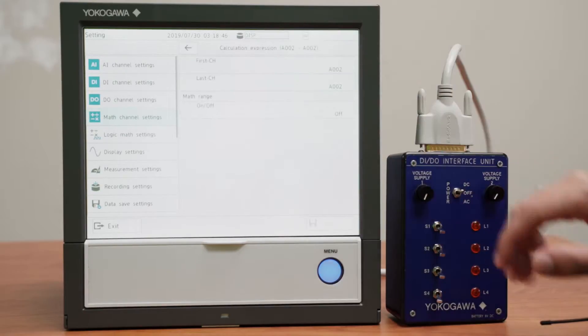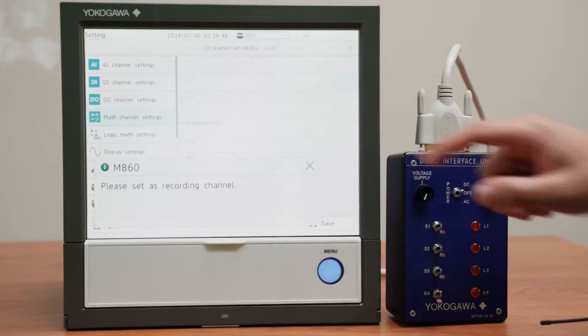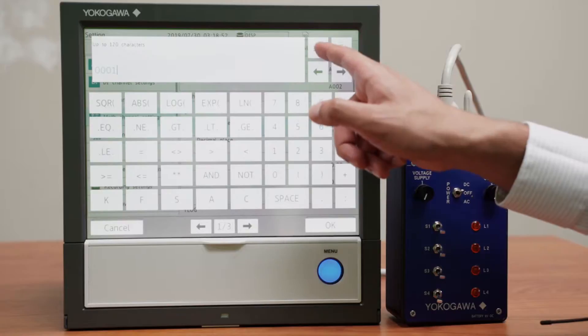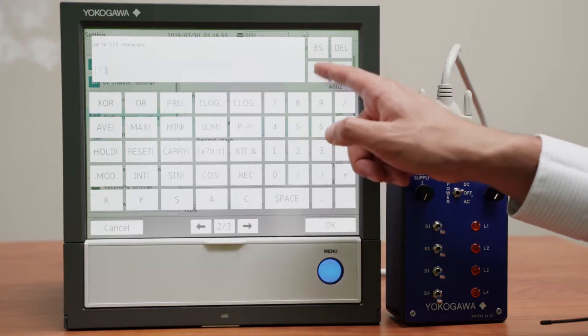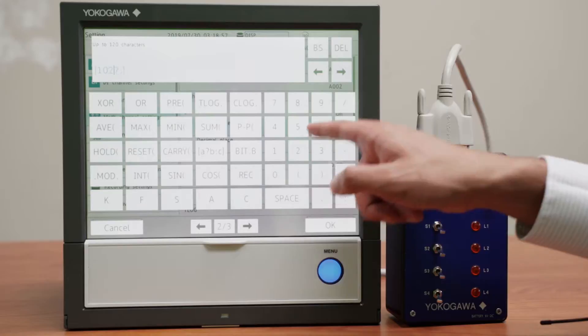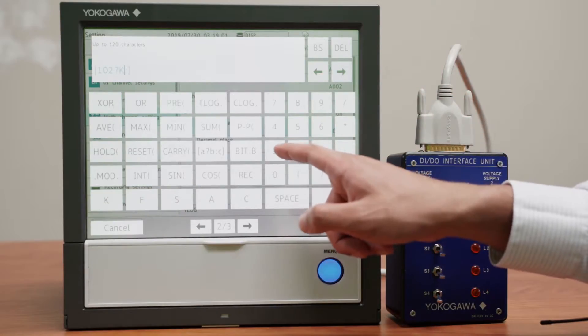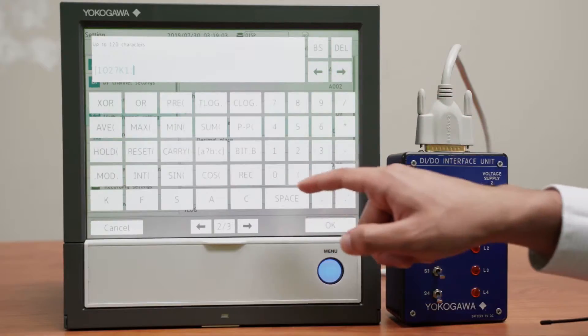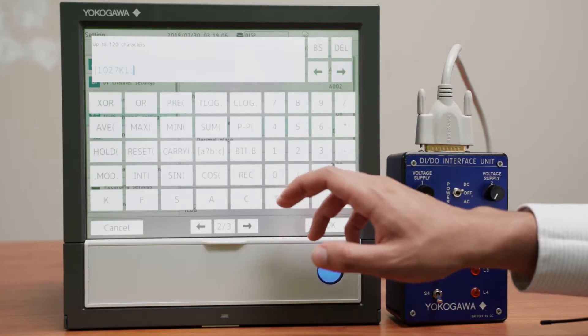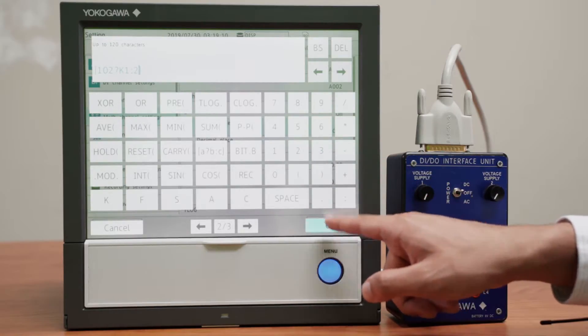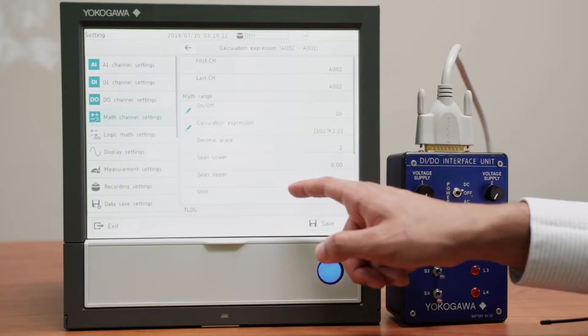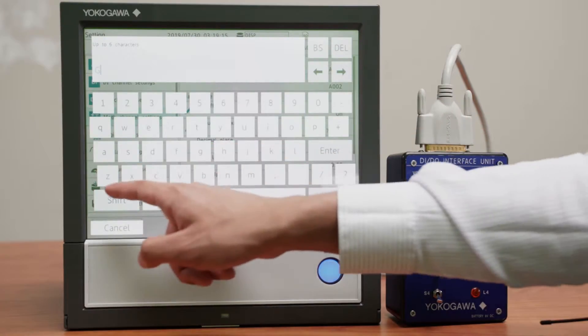We do the same thing for channel A2 except we do it for the second switch. This is channel 102. Will be equal to 0 when that is on. And if not, it will be equal to channel 2, analog input number 2. Unit will be gallons per minute again.